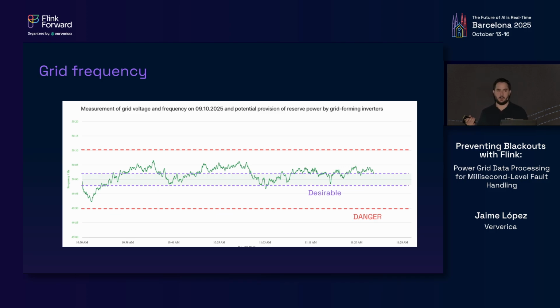The nominal set point in Europe is 50 hertz. In the US, in the Americas, and in some parts of Japan, it's 60 hertz. But here, 50. Every tiny deviation matters, and we are talking about very, very small maneuver bands, plus or minus 0.1 hertz of nominal. If your frequency goes beyond these danger points that I wrote here, pretty bad stuff starts to happen. In the extreme example, most generators will decouple from the grid if your frequency is too high or too low, so you suddenly exacerbate the problem and have, let's say, a vicious loop of cascading losses or additions to the grid.